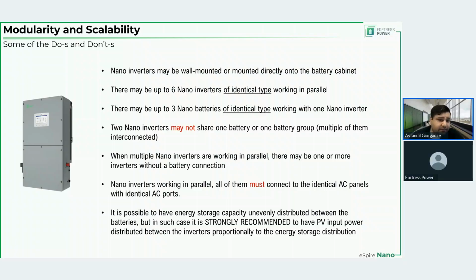As I said before, you can have inverters in parallel, but there cannot be more than 6 of these inverters in parallel, and all of the inverters will need to be of identical type. May that be the voltage type that they work with, or the output rating that they have. So, for example, you cannot mix 30 kilowatt 480 volt inverters with 60 kilowatt 480 volt inverters. And additionally, you cannot mix 30 kilowatt 208 volt inverters with 30 kilowatt 480 volt inverters.